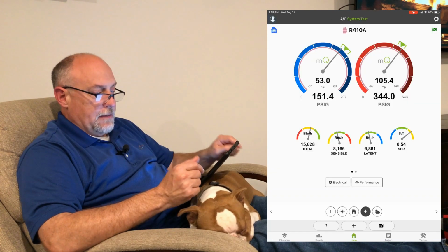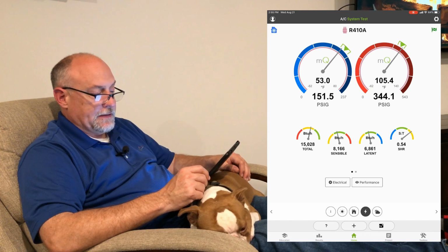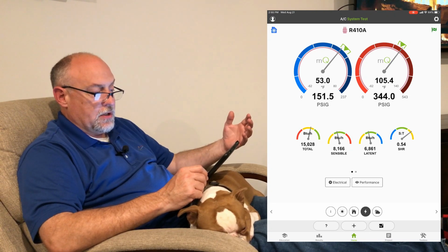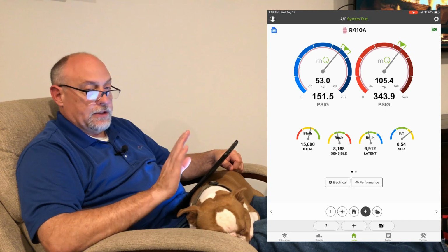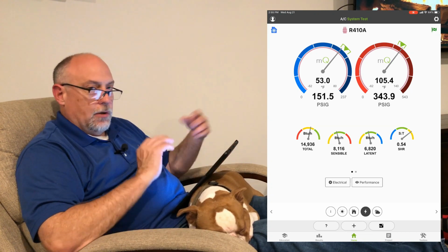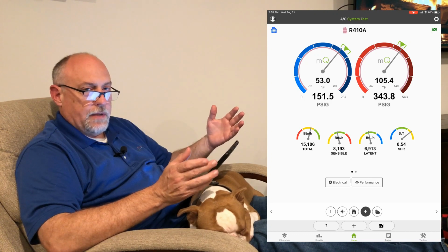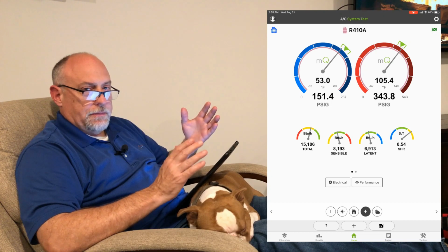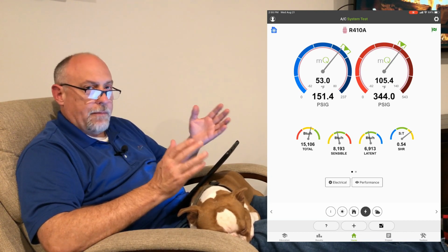So this temperature split's starting to stabilize here. You can see I have a slight increase in my total capacity, my sensible capacity. My sensible heat ratio is still running about 50-50. It changed just a tiny little bit, but my flag went from a red to a green, meaning the system's operating fine. This is a little bit less than ideal conditions, you know, to show you all this testing, but at least gives you an idea of what we can do in measureQuick with total system performance and how to really get that best operating well.